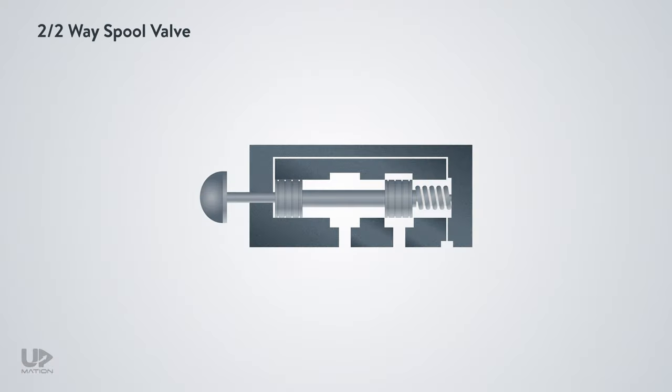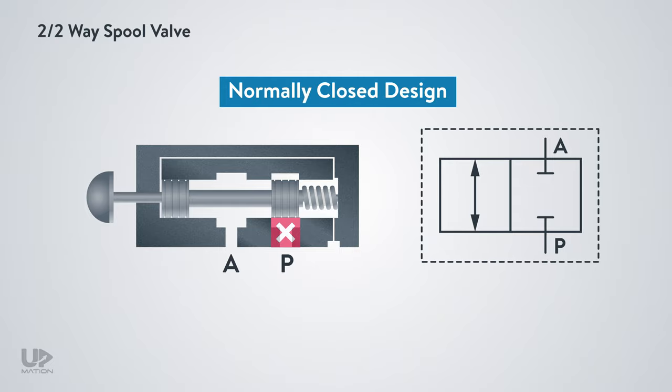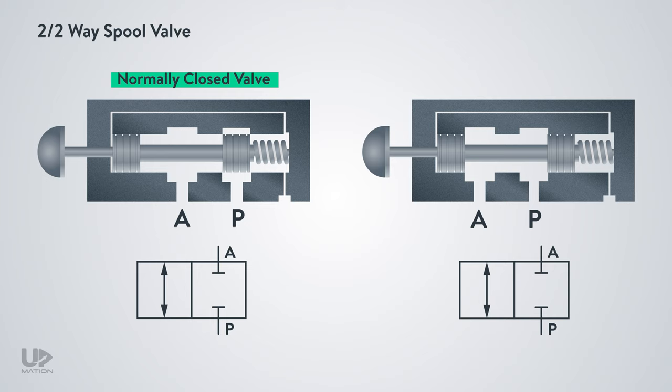For a 2/2-way valve, the valve has 2 ports and 2 spool positions. If in the normal or unactuated position of the valve, the spool blocks the P or power port, we can call it a normally closed 2-way valve with this symbol. But if we change the internal design of the valve in such a way that in the normal position, the P and A ports are connected and the passage toward the actuator is open, then this valve is called a normally open valve. Don't forget to relocate the squares with each other in the symbol.